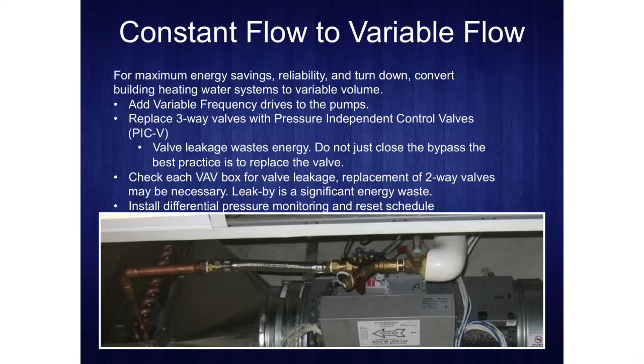And then fixing the known. When you go in to do retrofits on your laboratories, chances are, since you're currently flying blind without a dashboard that trends these points with easy-to-read graphics, you're going to find lots of failed components. Even though you think the lab's working perfectly, and you could put a flow hood on things and measure it, you'll find reheat coils leaking by, broken actuators, dirty ducts, all these kinds of things. This is your opportunity to make those laboratories safer and fix a lot of things you didn't realize existed. So expect to spend contingency dollars as you go through the project.